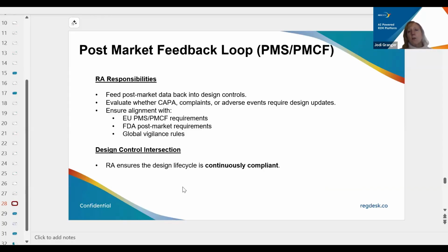The post-market feedback loop is also very critical, especially now with EU MDR. There are a lot of additional post-market requirements that have come into play as medical device regulation has evolved. It's important that the feedback you're getting on complaints, CAPAs, any adverse events, any design changes or updates, is fed back in through the process and assessed by regulatory. You need to ensure alignment at all times with your EU post-market surveillance plans. Sometimes you will have requirements from FDA for post-market as well. And in some countries, your global vigilance rules are going to change country to country.